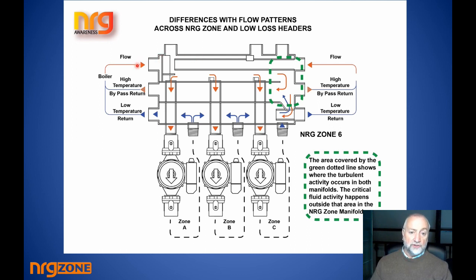So the water is going to do a couple of very, very important things. It's going to split when it hits the V-shaped baffle and go left and right if it's coming that direction, or it's going to split up if it comes through this pipe where a boiler is delivering on the right hand side, and then when it hits the inside of the V-shaped baffle, again it splits and breaks into the volume of the bigger pipe. But because the bigger pipe is such a larger diameter, the water slows completely. The laminar flow that would have come through the pipe from the left or right will now travel in a scattered flow from left to right, and any air in the system will be inclined to lift up towards the top, be trapped and taken away.